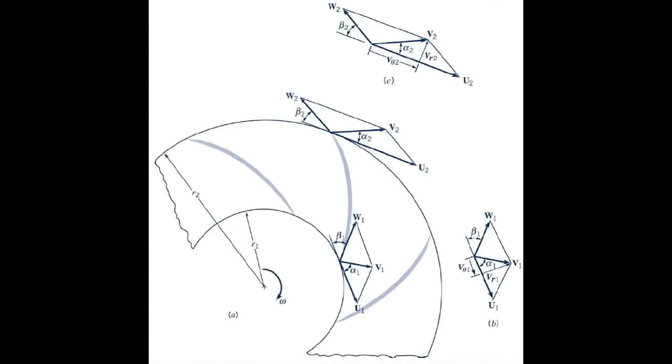So here's a figure representing the velocity triangles for the centrifugal pump. So this thing will be spinning around, has some darkened blades inside of it, inner radius R1, outer radius R2. Velocity triangle at the inlet, position one, has some relative velocity W1 relative to the fan blade, so coming in exactly tangent to that fan blade, and then has some fan blade motion. Normal to the radial coordinate, so tangent to that inner circle U1, then my absolute fluid velocity V1 coming in, have some angles alpha 1 and beta 1 representing those directions.